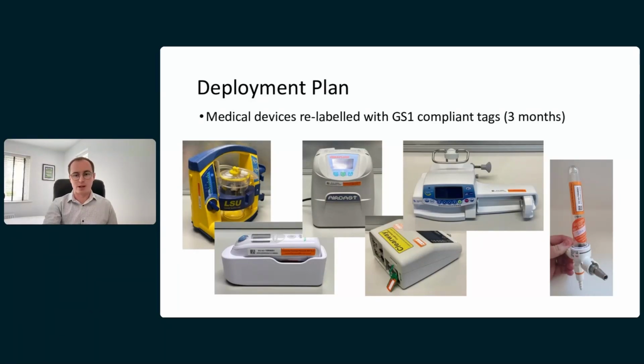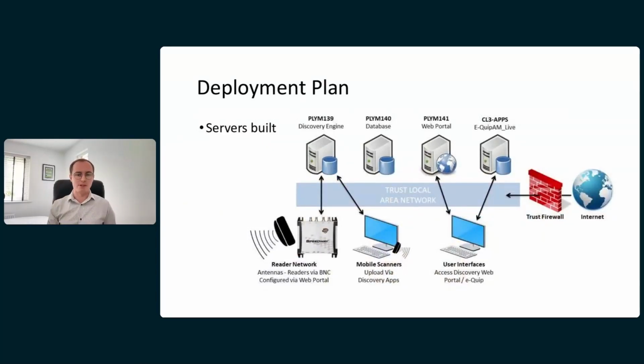In terms of the deployment plan, there were some servers and IT requirements that needed to be built. Whilst we were doing the labeling, that was all built in the background, along with the other project management elements. But it's very simple in terms of how it works. You have your tags, which are detected by readers, or antennas connected to readers. That gets pushed through to the Discovery, which is the RFID web interface. There are integrations between the RFID system and your existing medical asset management system. So as you go around searching for devices, or devices are detected, any alerts or outstanding maintenance on the parent database can be pushed through, and you can set up things like email alerts, notices and recalls that need to go out for specific devices.